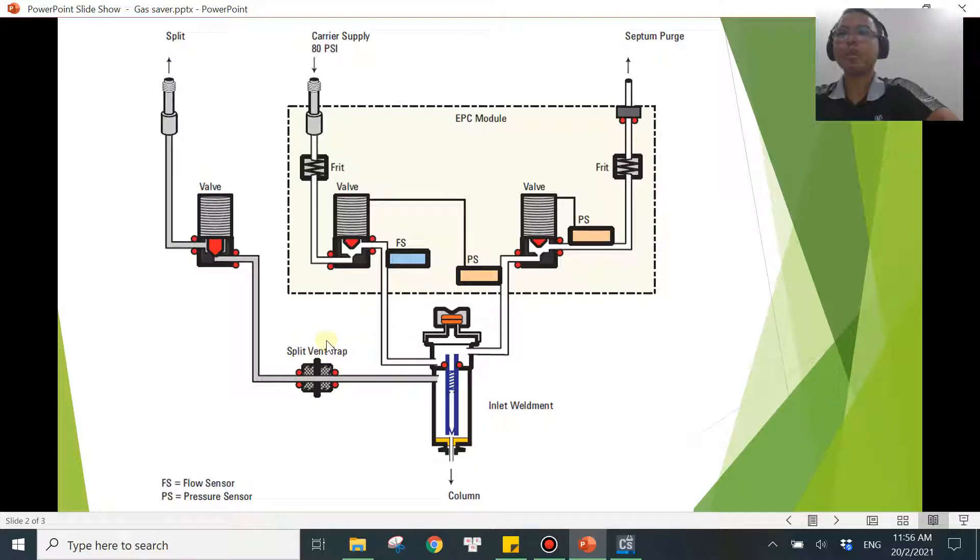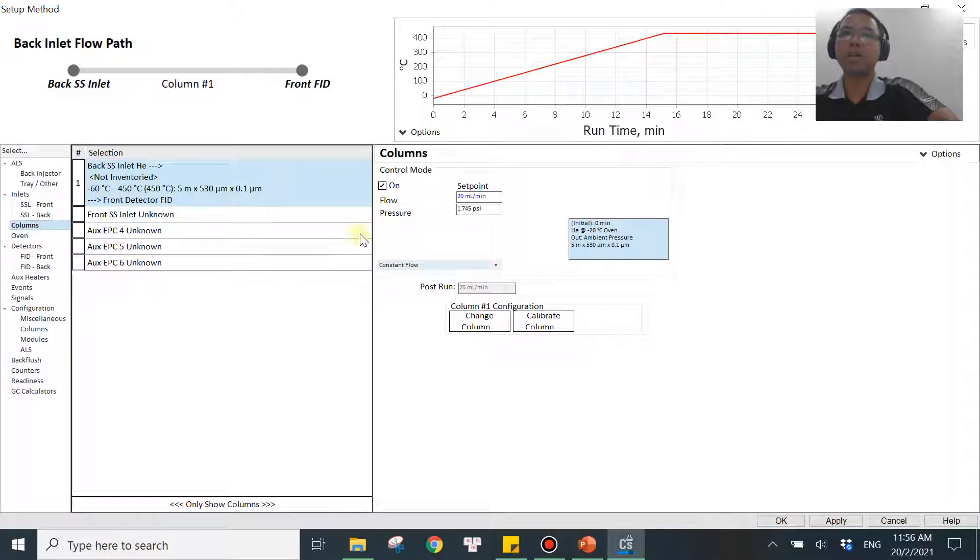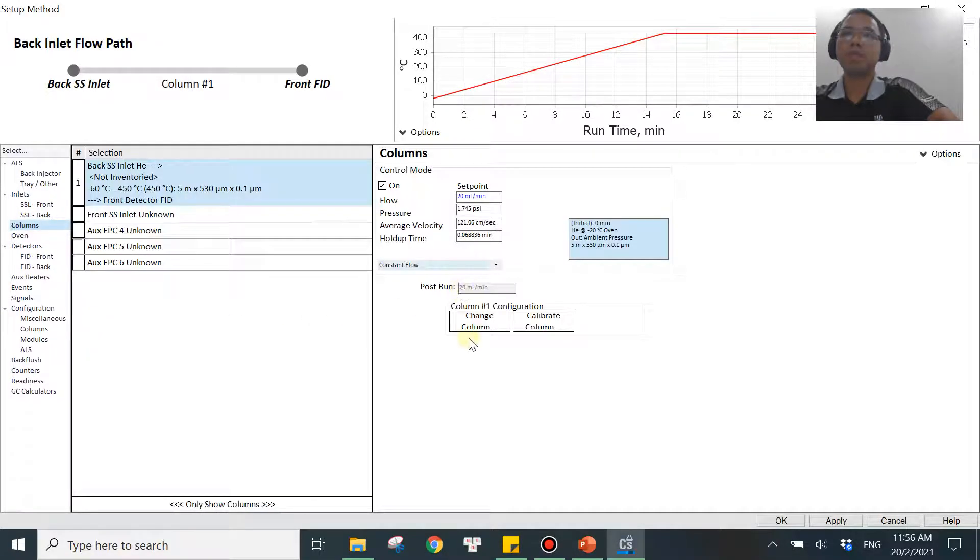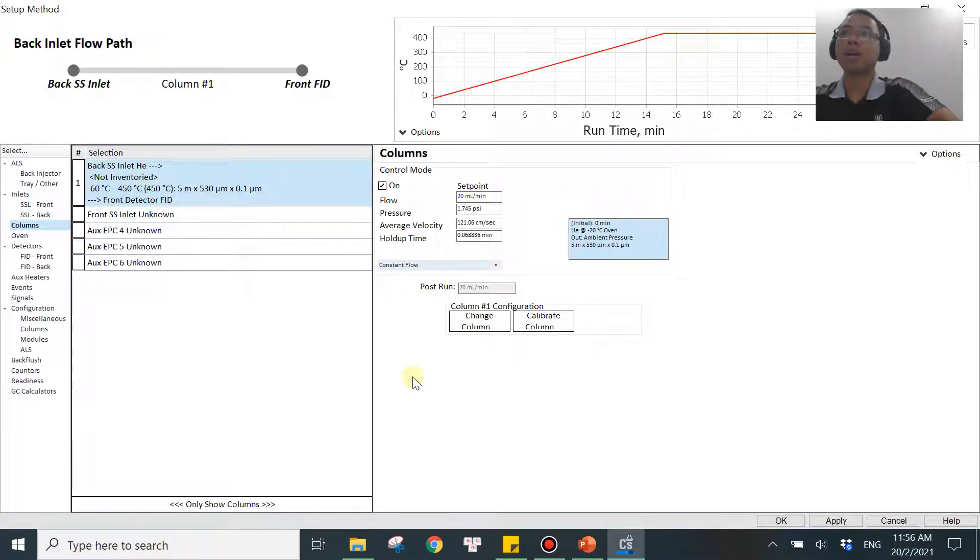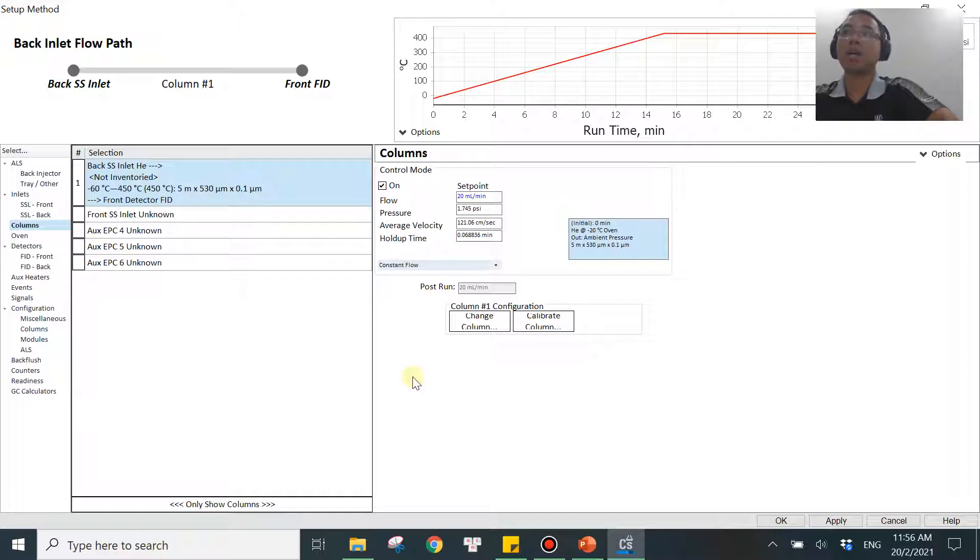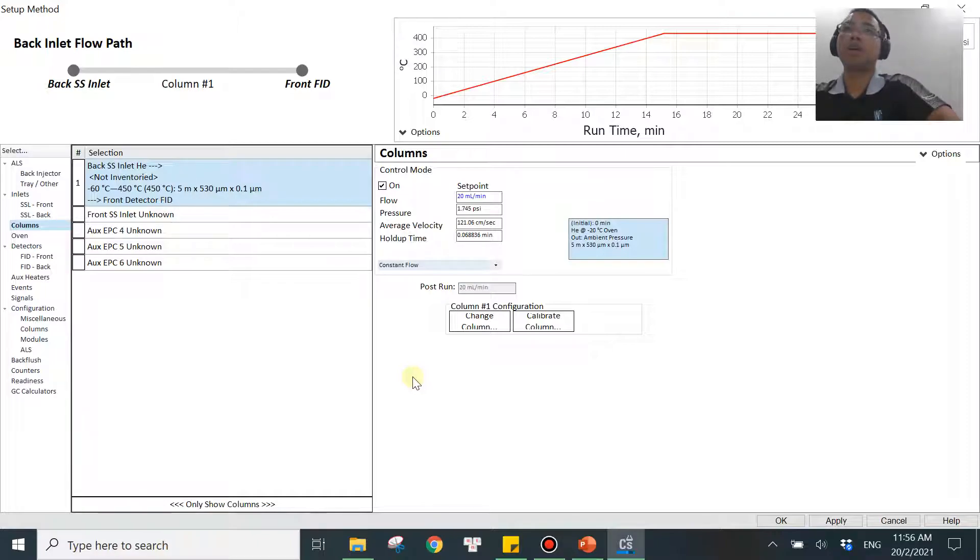So what if the scenario is that you increase the oven so fast that the pressure increase is not fast enough? Sometimes you will see something like the set point is always higher than the actual point. Then after a few times you will hear some beep beep beep from the GC. After a few seconds or a few minutes, the GC will shut down the pressure because the GC detects that there's not enough pressure to maintain the inlet pressure over there. So it could detect something like a leak or something like that. But in fact, it's not a leak. But the GC could detect something like a leak, so it could shut down the GC for you.